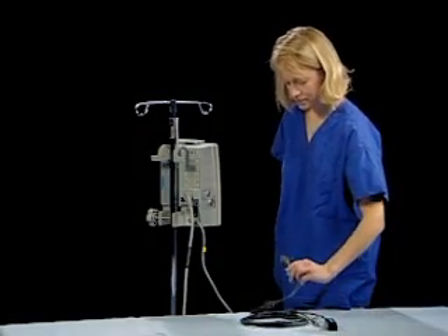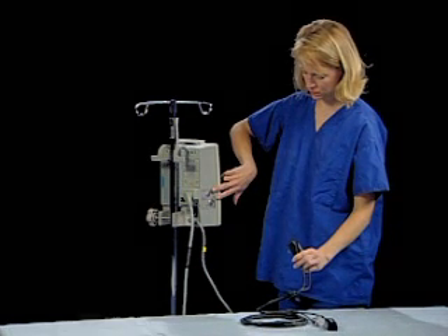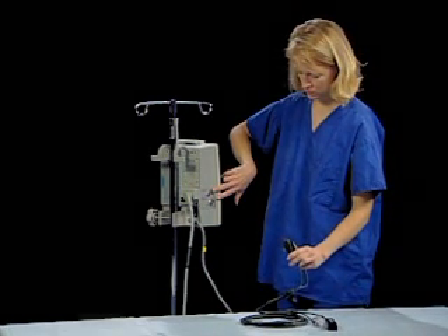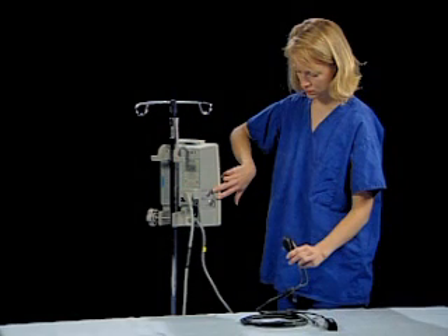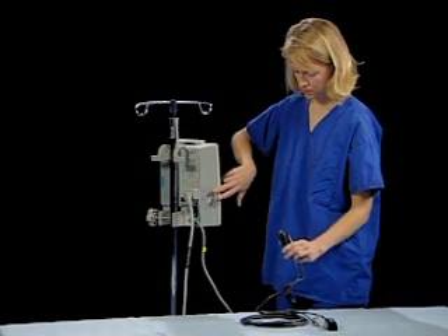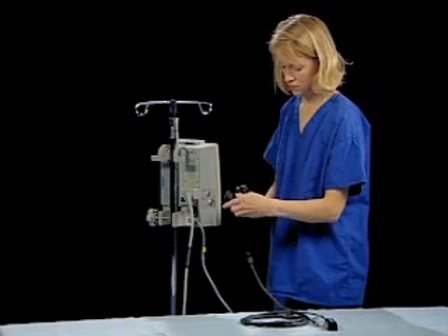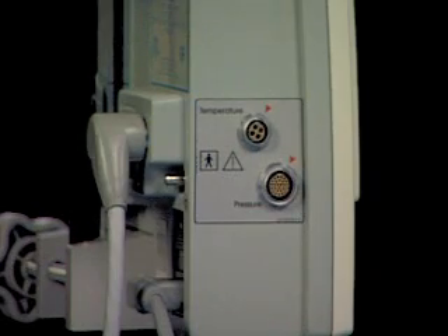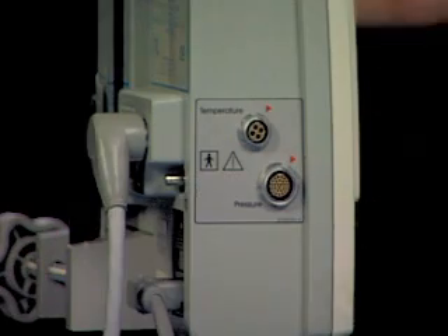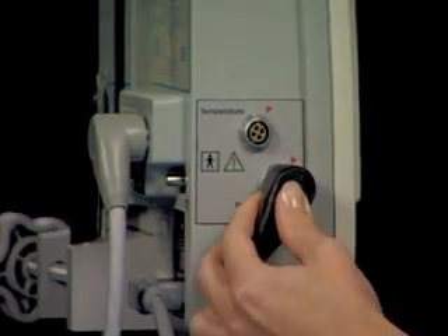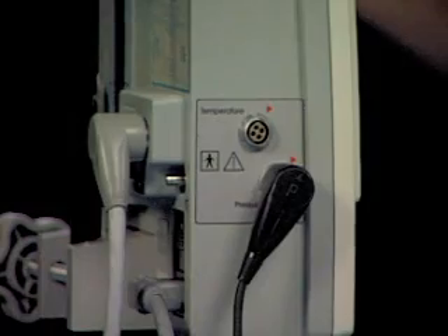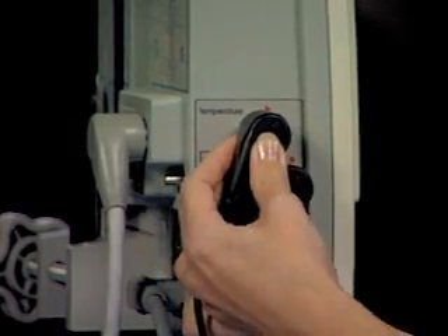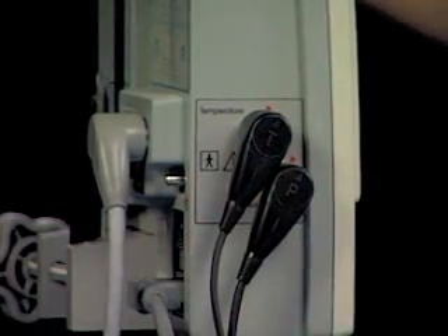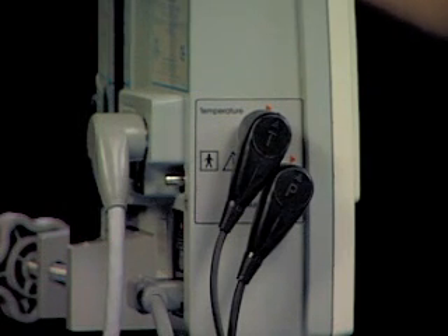The catheter preamp cable is attached to the two receptacles on the side of the monitor. This cable electronically transfers the fiber optic information from the ICP catheter to the MPM-1 monitor. Connect the preamp cable using the two appropriate pressure and temperature connectors. The cable connector, designated with P, connects to the pressure port, and the cable connector indicated with T connects to the temperature port. Align the arrow on the cable connectors with the red arrow on the side of the appropriate monitor receptacle. Please note, this cable is provided non-sterile.